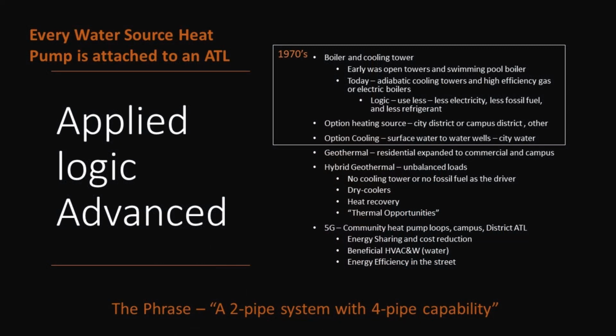Back in the 70s, it was a lower cost system, and you could do 2 pipes, and a tenant could buy his own units. We thought we were selling energy efficiency, but really what we were doing was selling the ability to put in your cooling tower, your boiler, run your main piping, and then as tenants came into the building, they could buy their own units, because you didn't know what the zoning was going to be. There are still jobs done that way today—several floors pre-sold, or a couple floors that aren't. So it was a simple logic.